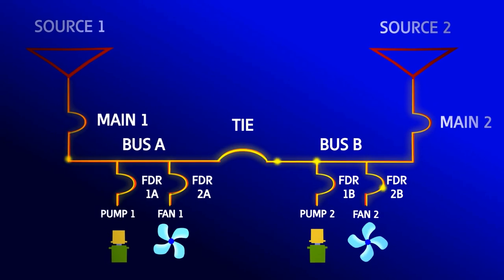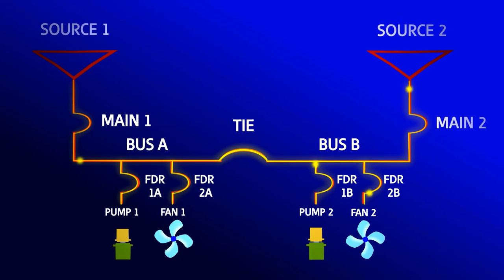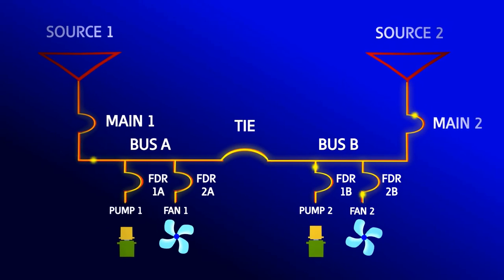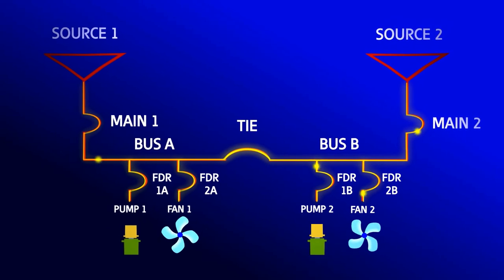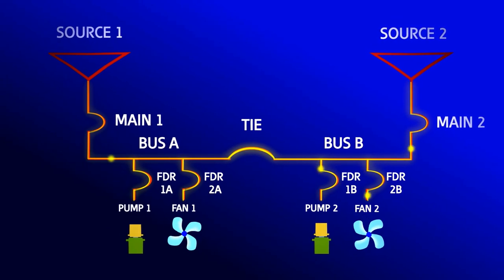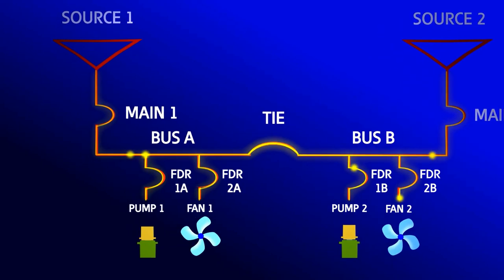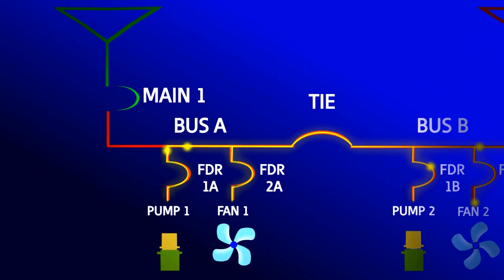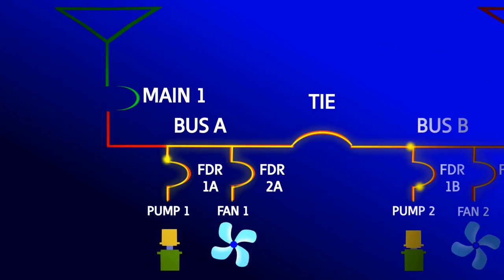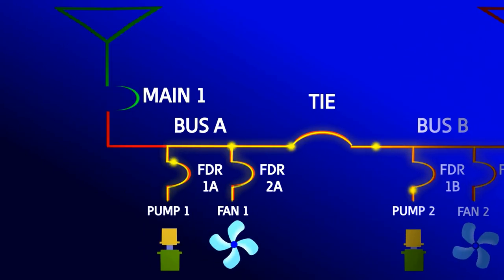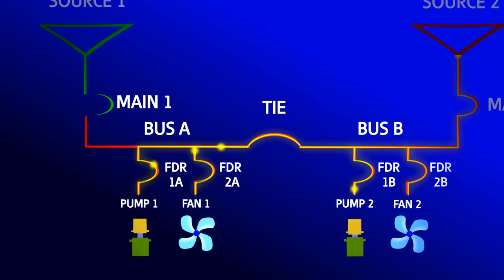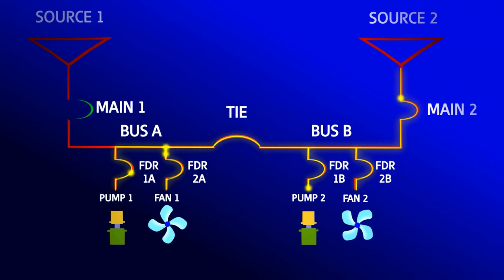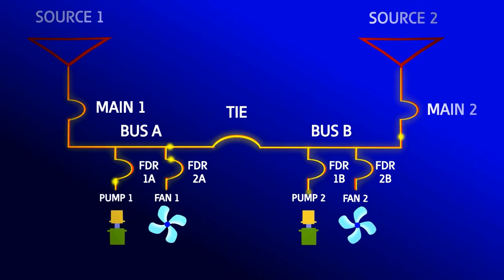In the case where the tiebreaker is closed during normal operation, both sources of power are running in parallel. When you lose one source, the other source automatically assumes all of the load. When the lost source returns, the sources are paralleled using synchronizing control.